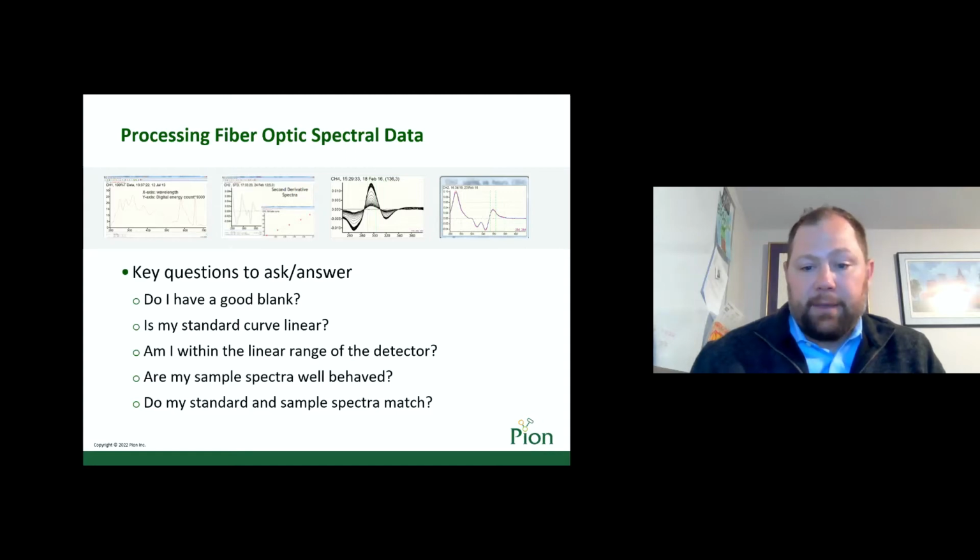the use of math. Basic baseline correction techniques like line or point work well for filtered samples or samples with scattering from large particles. But when scattering is caused by small particles, Tyndall and Rayleigh scattering dictates the baseline. Second derivative does a better job at removing the effects of this scattering and allowing for accurate quantitation of the analyte of interest. While second derivative spectral interpretation is powerful, it must be applied properly in order to not report on artifact data.